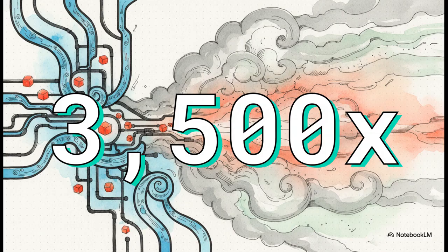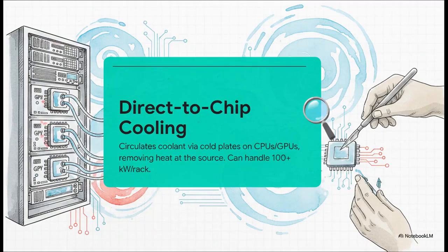It's just a fundamentally better tool for the job. The most efficient way to use this amazing property is with direct-to-chip cooling. Instead of trying to chill an entire room and hoping some of that cold air finds its way to the processors, you bring the coolant right to the source of the heat, the GPUs and CPUs. It's the difference between being a surgeon with a scalpel and just flooding the entire operating room. That precision is what lets it handle insane densities, well over 100 kilowatts per rack.